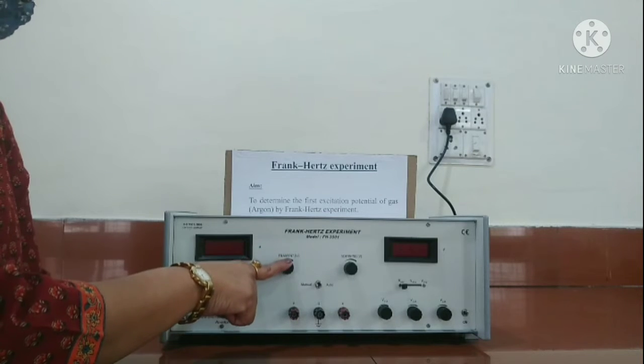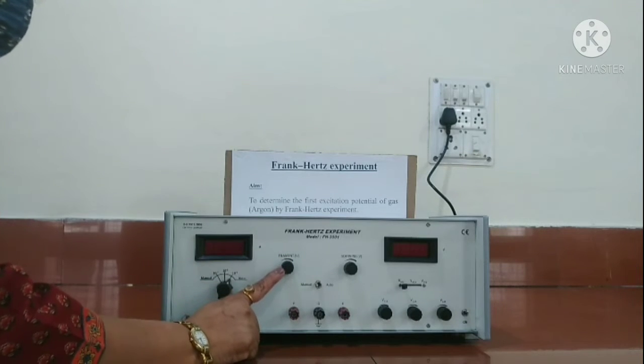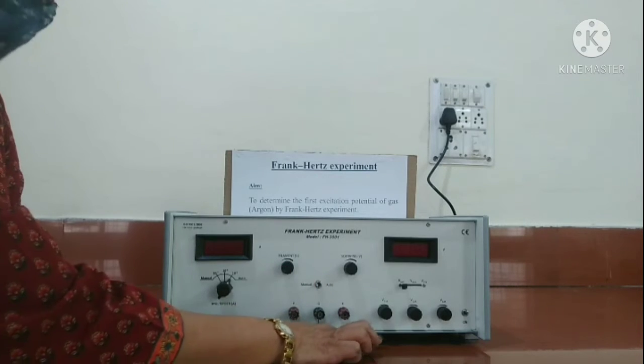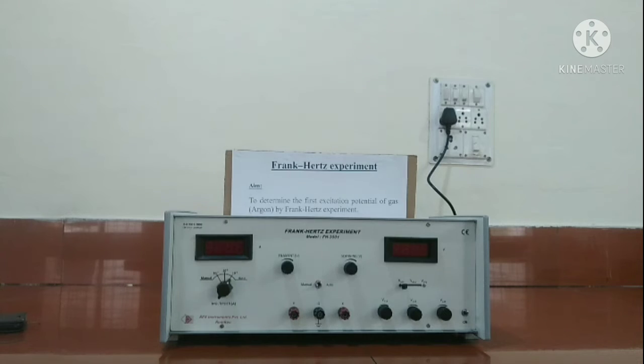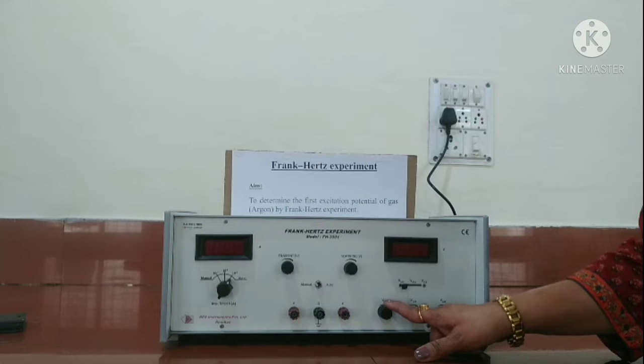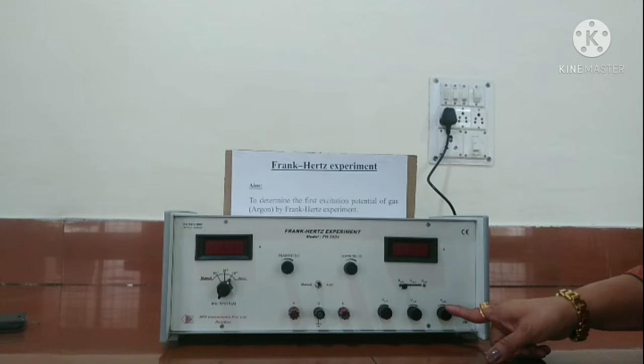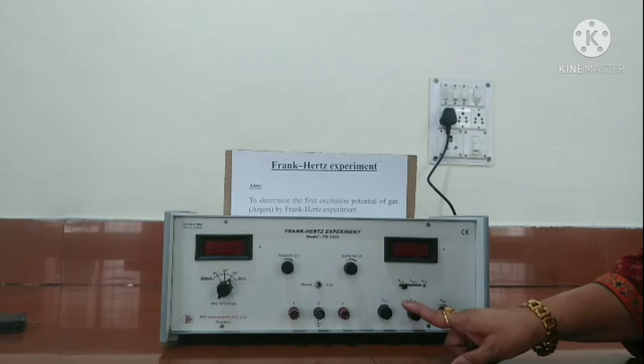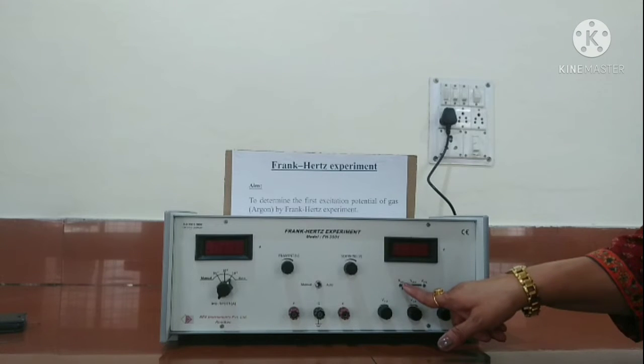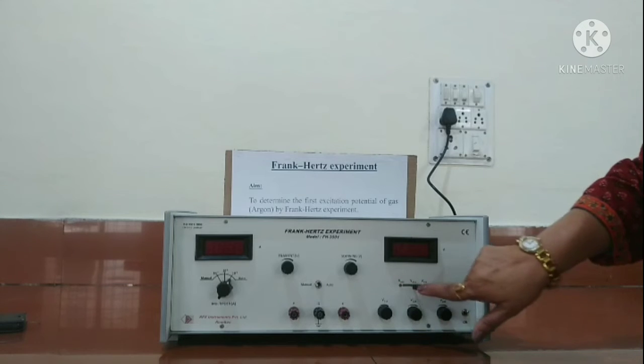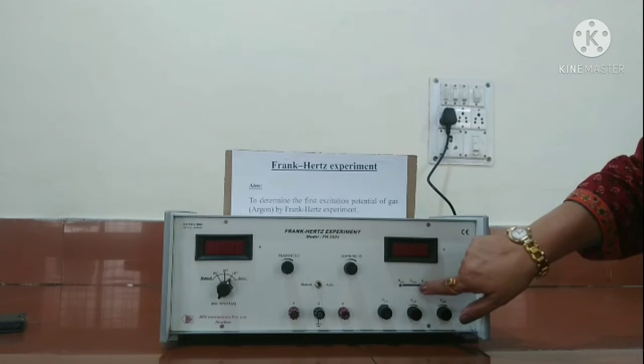This is the filament voltage. We can apply a voltage. Whenever filament voltage is changed, please allow 2-3 minutes for its stabilization. These are the knobs for changing the voltage with respect to G1K or G2A and then G2K. Accordingly, we have to flick this switch for G1K, G2A, and G2K.